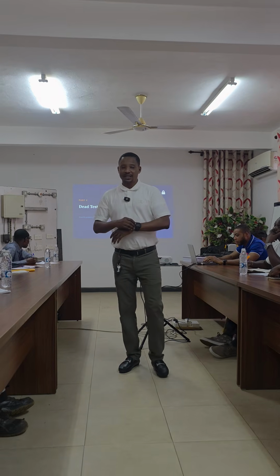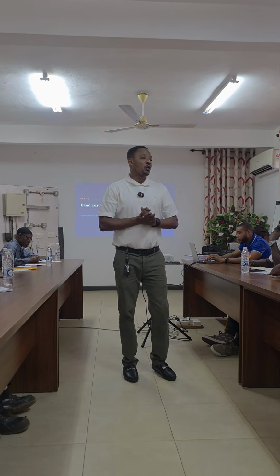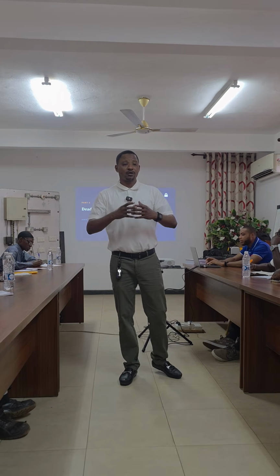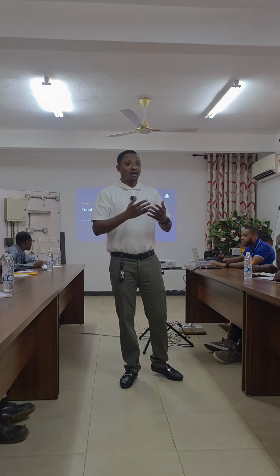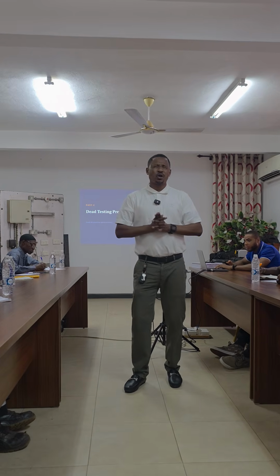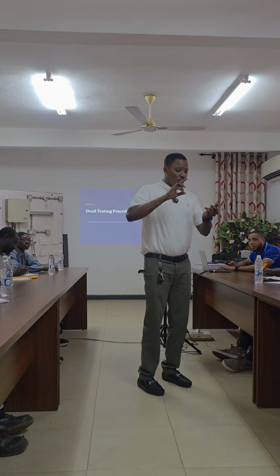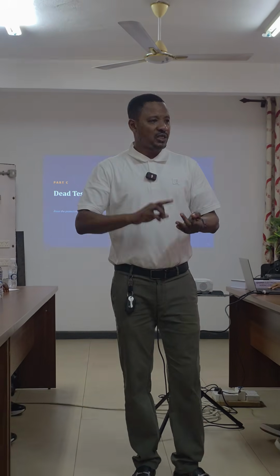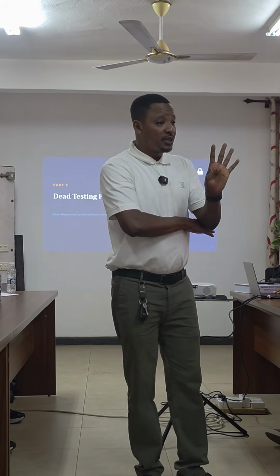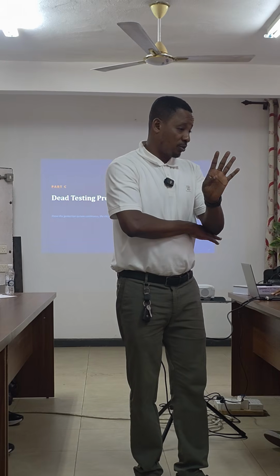At those tests that are done when the building is completely de-energized. So if you are doing what we call the current practice as far as the Energy Commission is concerned, which is what we call the minor or basic testing, you are required to do continuity, polarity, insulation resistance, and earth electrode resistance tests. It is upon completion of this that an inspector can issue a test report.